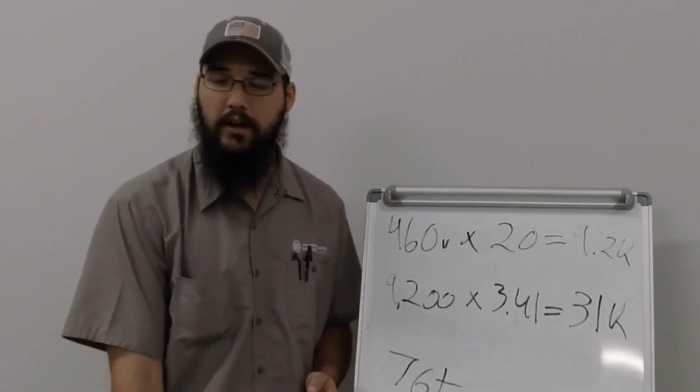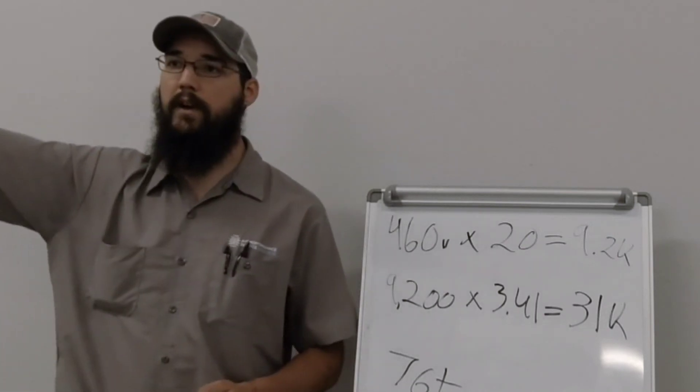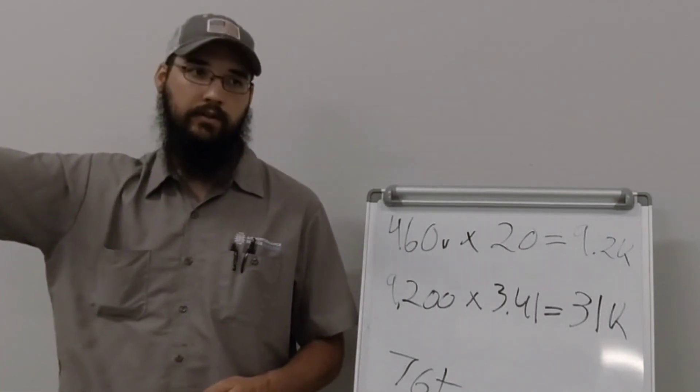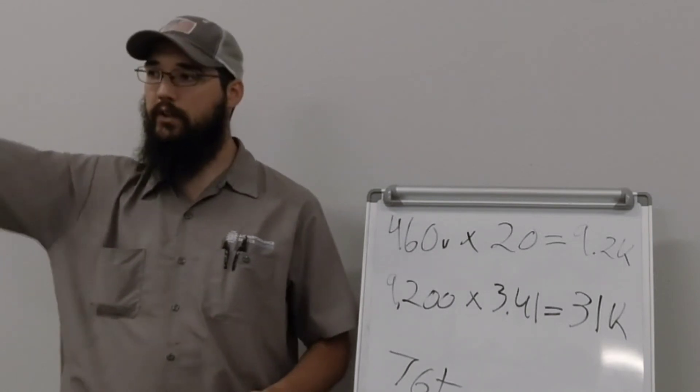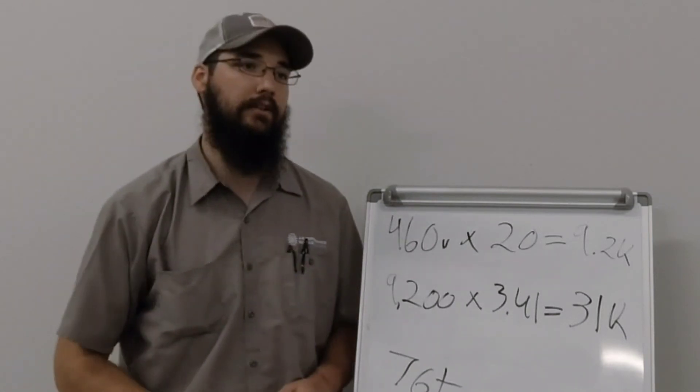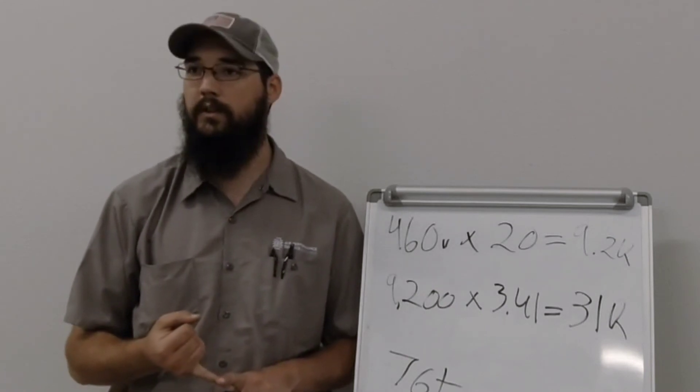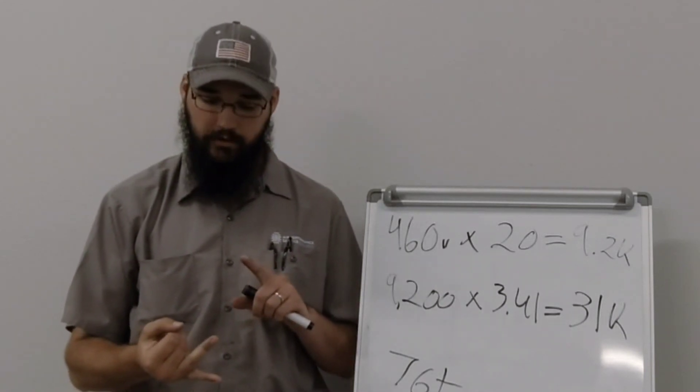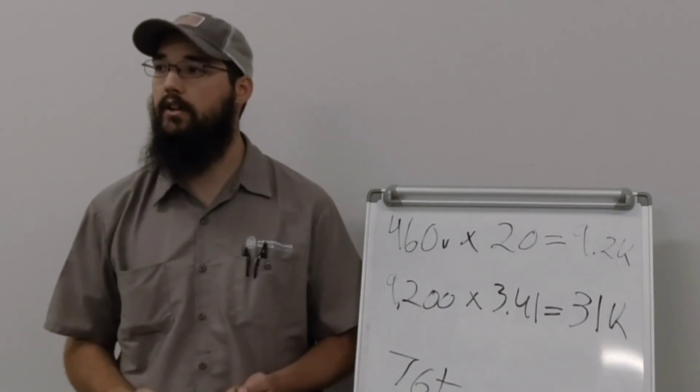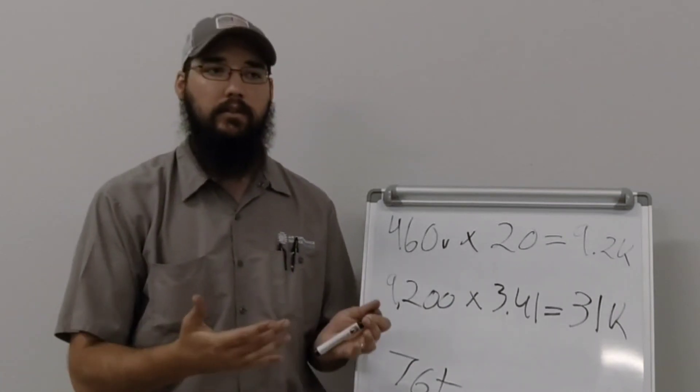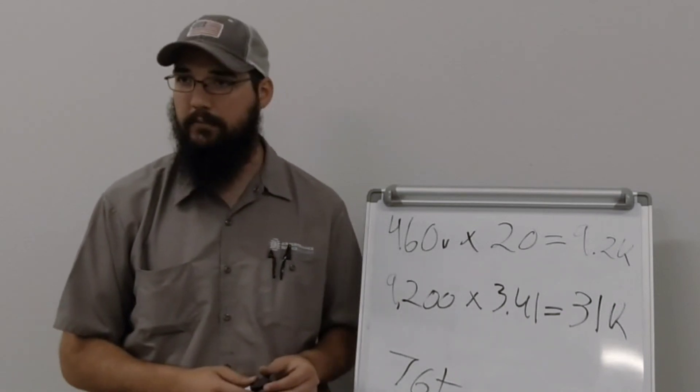We need to adjust things to run higher saturations that counteract each other. If you're struggling with not enough humidity in space, find ways of increasing the saturation on the equipment. Right? And if it's the vice versa, too much humidity, you've got to lower that saturation down. Whether you do it by reducing the total volume of air being moved or whether you do it through the metering devices, through the staging of the compressors, however the heck you do it, that's how we can accomplish that.